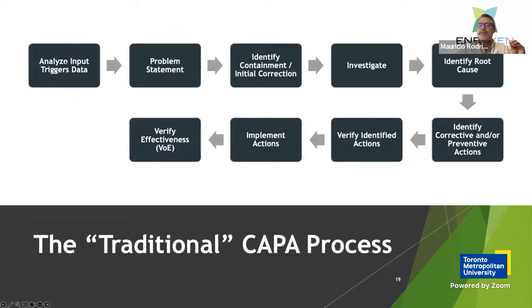When a nonconformity is discovered, the next step is to analyze the available data and generate a problem statement. Corrections must be identified as early as possible to ensure containment of the issue. For example, if there is product in the field, we need to be able to take an action to recall or take that problem from the hands of the users in order to avoid harm.